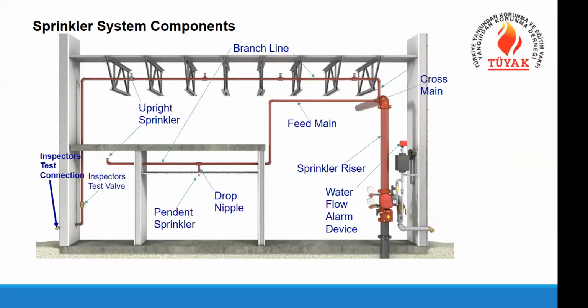So when a sprinkler operates inside the building, you can have a signal, electrically or mechanically, sounding an alarm to tell you that there is a fire in the building. So everyone can evacuate the building and the fire brigade comes. So this system is working as an alarm system as well. Without having any detectors, the sprinklers are detectors themselves for the fire.